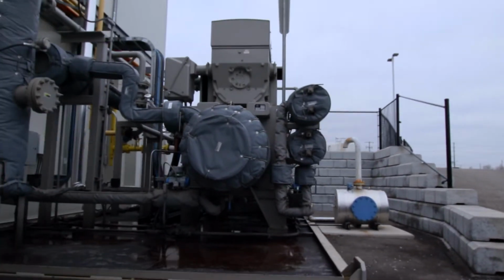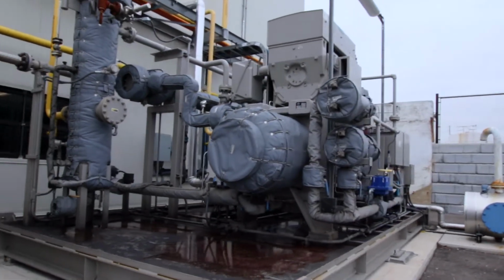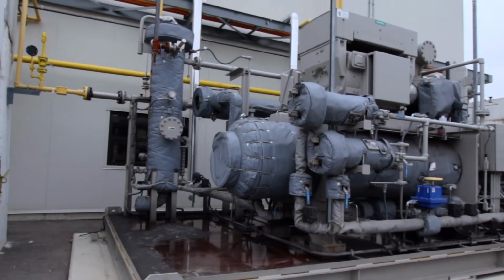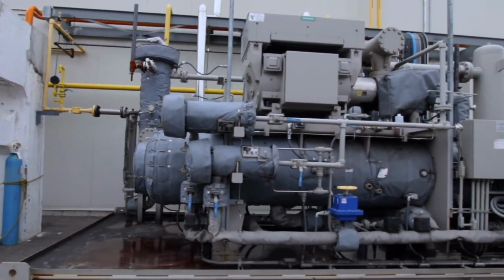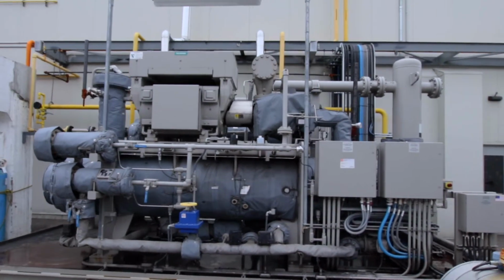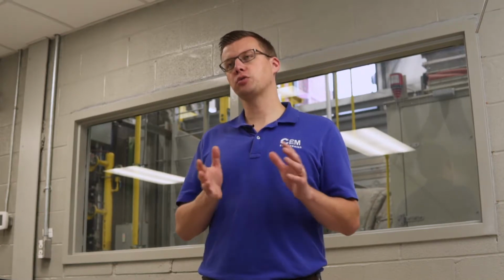We have a Vilter fuel gas booster compressor here. It's a single screw machine. Vilter is part of the broader Emerson family of companies, and it's been a very reliable unit. It's one of the most critical, because if the gas is not at pressure, the turbine won't run and nothing else will happen. So the gas compressor is really critical.